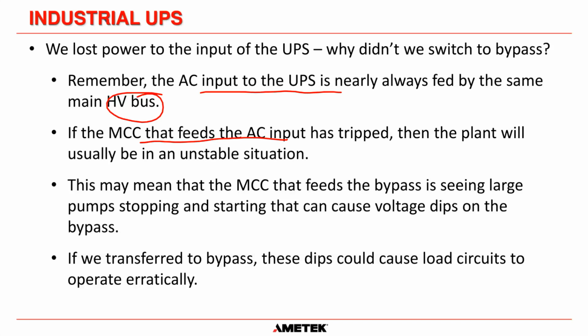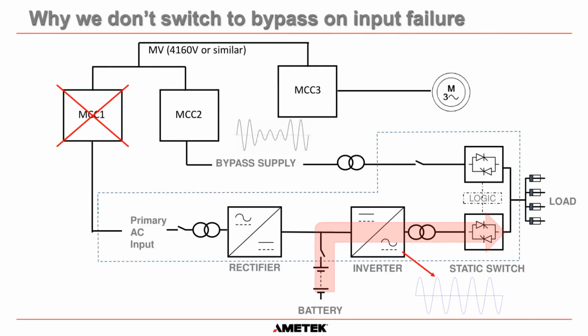And while all those tripping functions and changes are going on, the AC voltage and frequency are going to start moving all over the place. It may mean that the bypass within the plant, even though it's fed from another MCC, is being subjected to large pump stopping and starting that can also cause voltage dips on the bypass. So if we transfer to bypass, those dips and blips could cause load circuits to operate erratically. And we don't want that, okay?